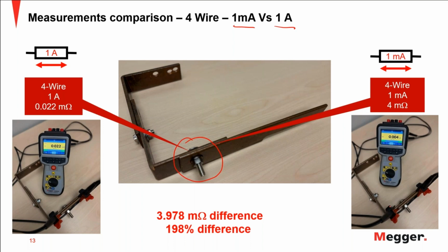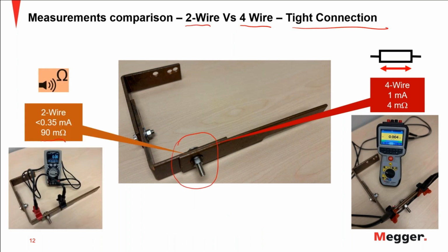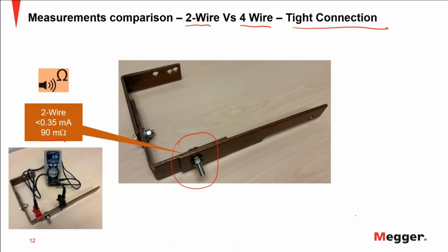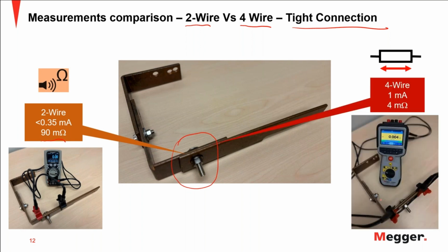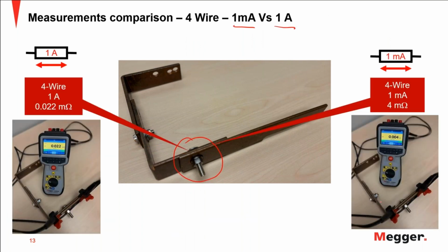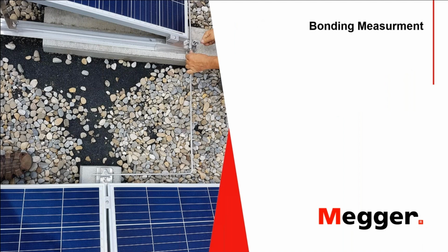So now I can see the real resistance of the connection. And if I use this result of 90 milliohms to calculate how much heat is going to be dissipated there, it's going to give me a very high result. And that's what you don't want when you have a bonding. You don't want to have a high dissipation of power. Now, for bonding purposes, you don't have current constantly flowing through that connection. So let's talk about bonding and see what the definition is and what the standard says.